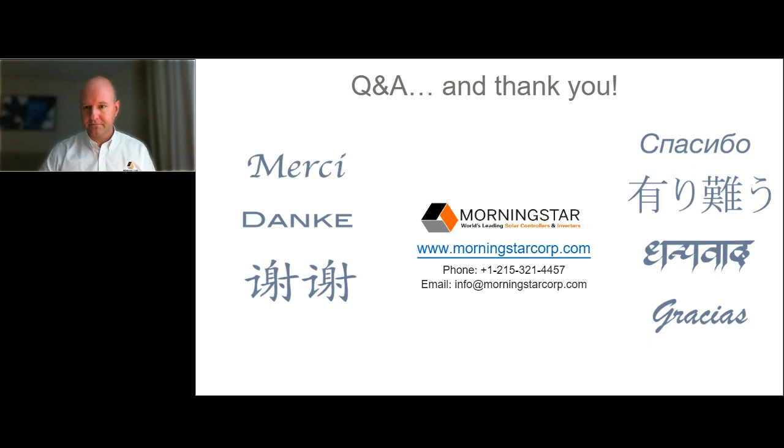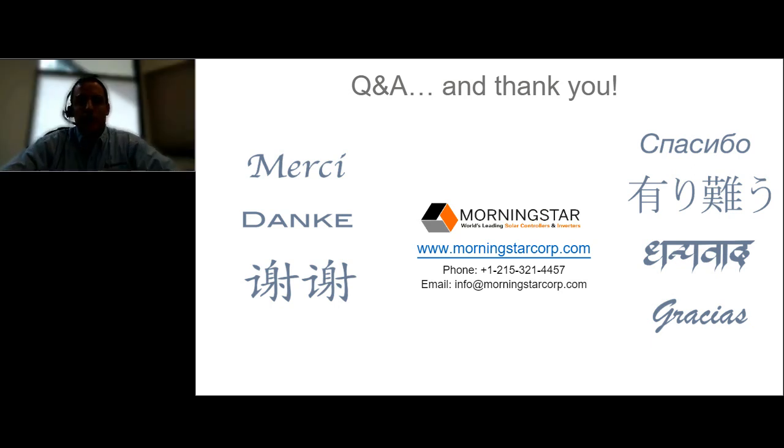Yes, I can take that one. So we have a conformal coating process that we apply to all of our circuit boards. Depending on the product in our family, it may be encapsulated in epoxy. But for the products that we're discussing today, the circuit boards are applied with a conformal coating process that's actually machine controlled. The conformal coating is a very thin, translucent layer that is sprayed over the circuit board and all the associated parts, so that if there's condensation or bugs or whatever that happen to be walking across the circuit board, it prevents those short circuits at the board level.